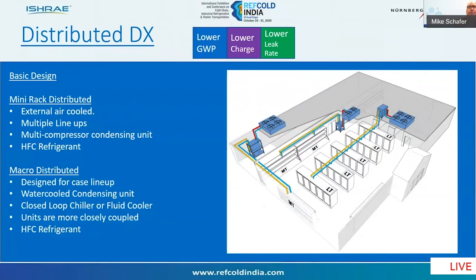Transitioning to a distributed DX system, this type of system employs all three strategies: lowering the GWP, lowering the charge, and lowering the leak rate. The basic design is essentially that you have a number of smaller racks located closer to the evaporators or to the cases, with the intent to try to minimize the length of run of the refrigerant piping. These would typically have external air-cooled condensers, but could be a multi-compressor condensing unit. And as I mentioned, it would service multiple case lineups and be using an HFC refrigerant.